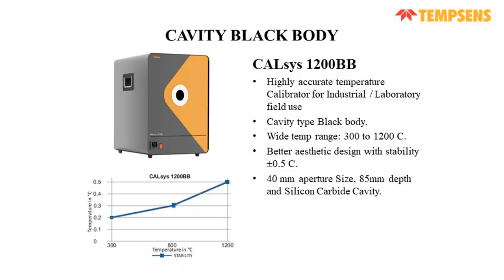Next, we have the cavity black body. Like we had the 1200L for the dry block, we have the 1200 BB for thermal imager and pyrometer calibration. It is a cavity type black body, where a cavity is inserted, and it is for laboratory purposes. All the models I discussed earlier were portable models that you can carry for on-field application. The weight of those models is around 10 kgs, 12 kgs, 15 kgs. So this one is for laboratory purposes and industrial calibration, and the cavity will be inserted.